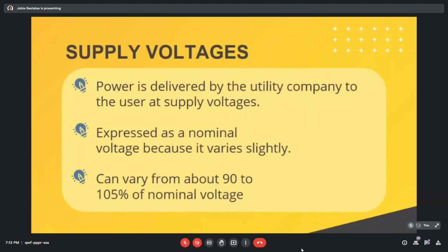Supply voltage is where the power is delivered by the utility company and expressed as a nominal voltage because it varies slightly. Nominal voltage is a value assigned to a circuit or system of a given voltage class for the purpose of convenient designation. That is why supply voltage is expressed as a nominal voltage. During normal conditions, supply voltages can vary from about 90 to 105% of nominal voltage.